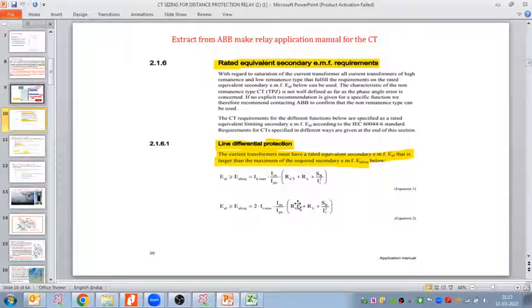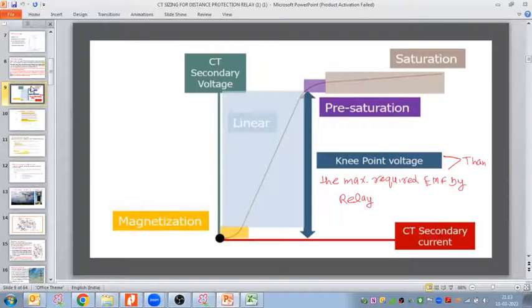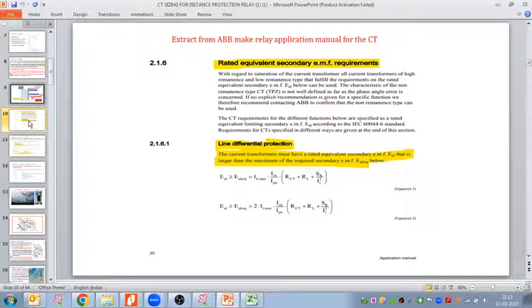So the correct method is to take the relay you are using, what kind of relay you are using. Based on that, take that particular relay application manual. We also briefly discussed which kind of relay we have to use, what relay or what model we are using. From that relay applications manual, open it or download it from Google or the manufacturer library, go to the CT requirement page, check the formula, and based on that calculate the CT knee point voltage requirement.